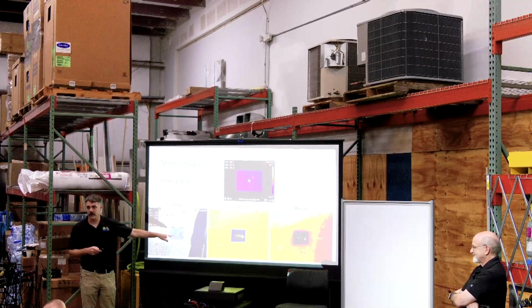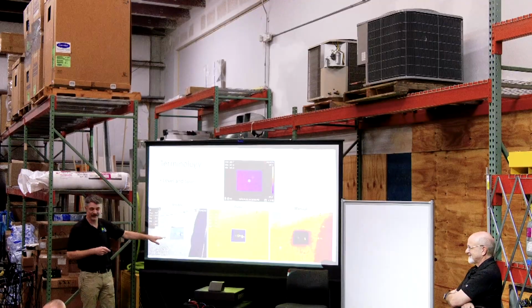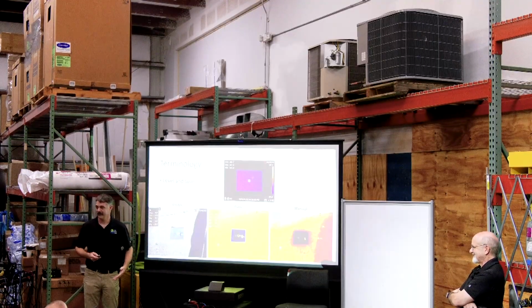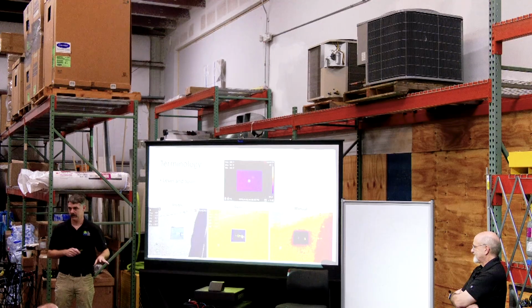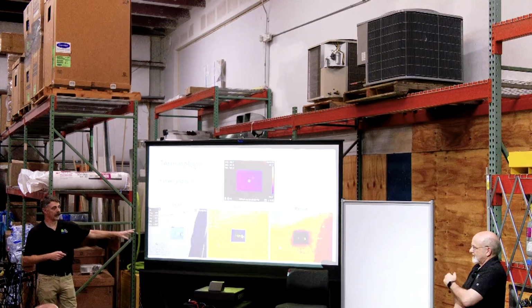Now, how cold is the sky? It's freaking cold. All right, we don't have coats for that, especially not here. This is Florida. But it's trying to read the temperature of the sky, which is why it's less than minus 22 degrees, because it's reflecting back up and trying to read the temperature of the sky. This is part of knowing the material that you're looking at.